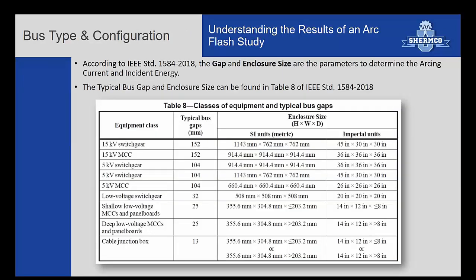And like I was saying, the gap in the space that the arc can occur in depends on how much current would flow. So the bigger the spacing, the more voltage drop, or voltage difference, you're going to have, and the less current you're going to have. So IEEE 1584 gives, for typical switchgear and panels, what the enclosure size and this gap should be used in your study. And most software, SKM, ETAP, EDSA, all have those numbers built in.